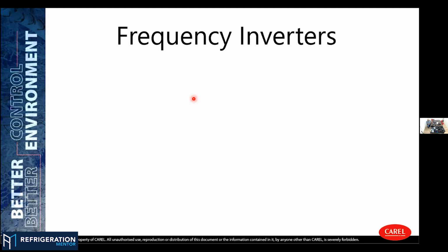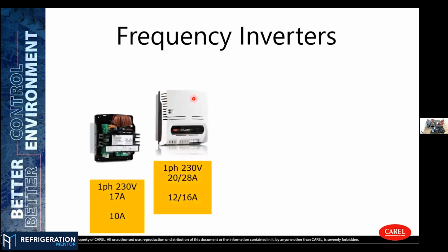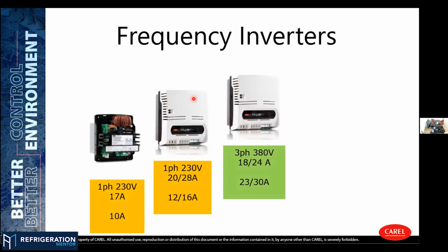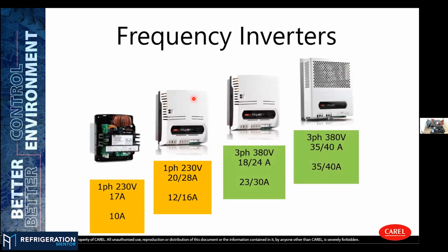And to do all this magic, we need some frequency inverters. We have different types of inverters, both single phase and three phase versions. Some of the motors, depending on the type of motor we are using, can be operated using a single phase 208 or 230 volts application. So for the US, you can just use two phases in order to make it run in a single installation.